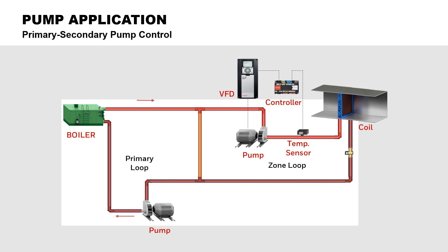When the secondary loop water temperature starts to drop, the pump ramps up, pulling warmer water from the primary loop. When the secondary water temperature is at or above set point, the pump slows down. The loop cools off as less water from the primary loop is introduced into the secondary loop.